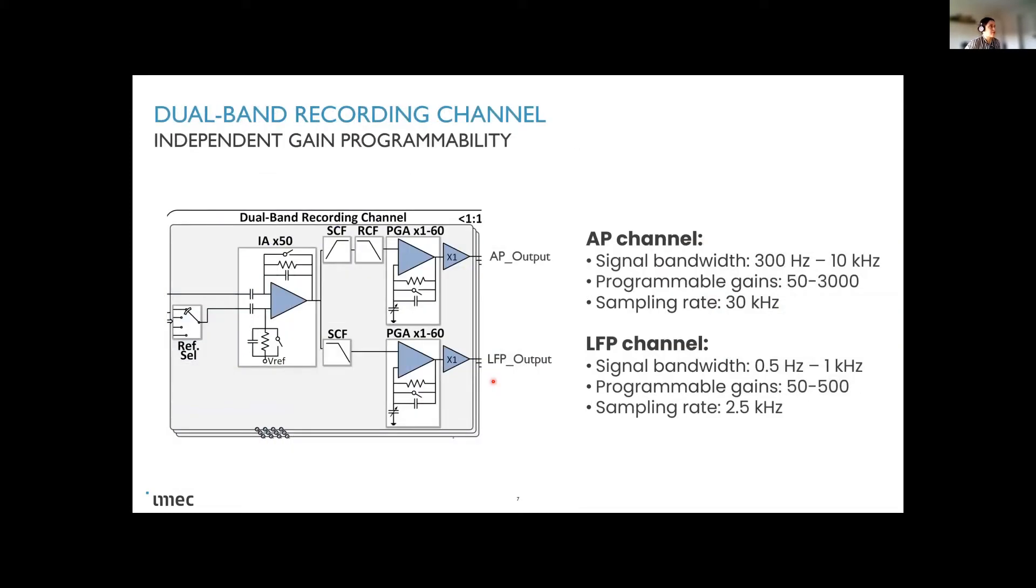Here you have some details of what we call the dual band recording channel. Basically what we do here with this dual band is to separate the AP signals from 300 hertz to 10 kilohertz. This filter is done on chip, it's a first order filter. So for the people that need better filtering, it's better to apply additional filtering outside of the chip in the digital domain. And the local field potential filter is from 0.5 hertz up to 1 kilohertz. And here the sampling rate is a little bit lower for the LFP channel.